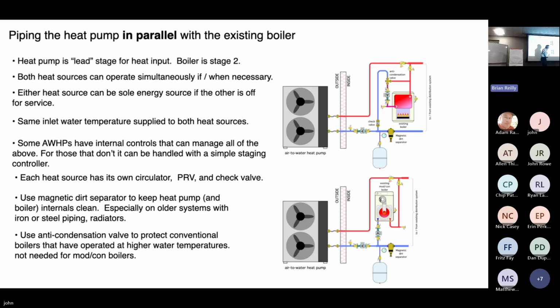I just want to stress the circulator in each one of these. A little hard to see it, but right there is a check valve, and right there is a check valve. It's important when you have two circulators like that and they're in parallel piping branches. Each has to have either an internal check valve built into the body of the circulator or an external check valve. Anybody know what'll happen if those check valves aren't there? Let's say one circulator's on and the other one's off.